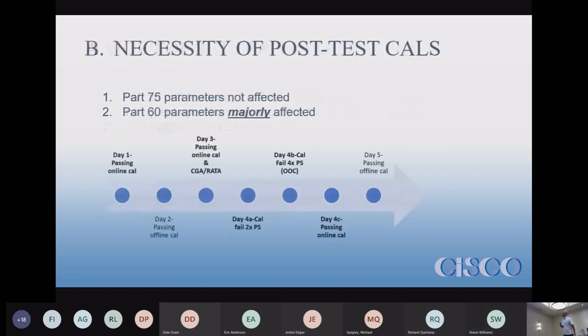Can I just ask real quick? No, go ahead. How would the offline cal affect me? So, specifically Part 75 allows you to do what's called an online/offline determination. What it permits is, if you have an offline cal and an online cal within 24 hours of each other that have passed the normal performance spec for Part 75, you can use that as a daily calibration check. But ultimately, over 26 unit operating hours, which could extend days, you still have to get an online cal. But for the normal daily cals, you can get away with using the offline cal. That makes sense.